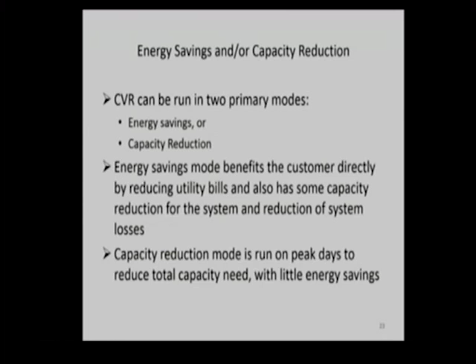There are additional benefits from CVR. You get some reduction in grid losses. Most of the savings in energy is behind the customer meter. So your refrigerator runs more efficiently, your air conditioner runs more efficiently and uses less energy. But there are also some savings in the grid itself. There are losses in the grid, and when you lower the voltage, it lowers the energy that's lost in the grid. But it's only about 5%. 95% of the savings are actually in the customer's homes.